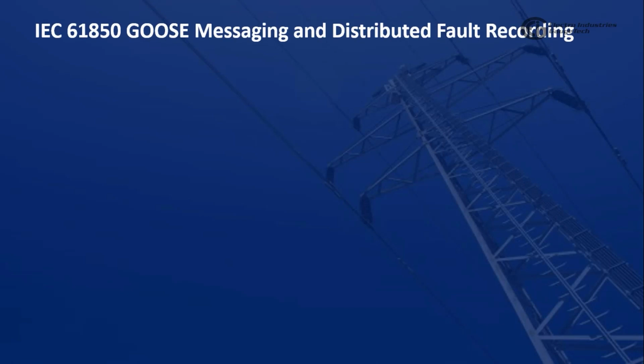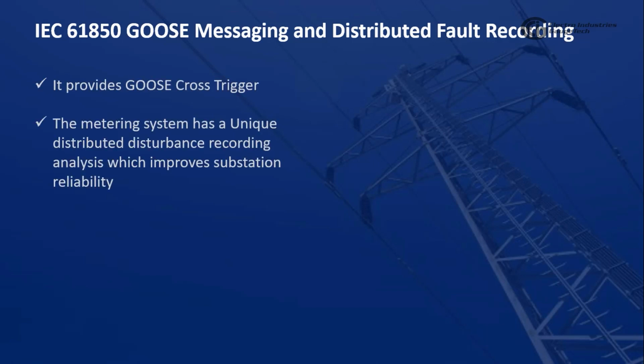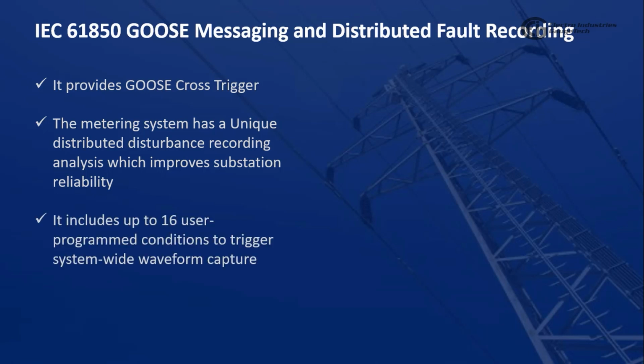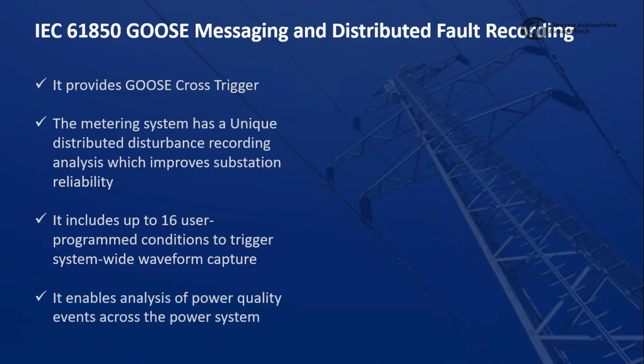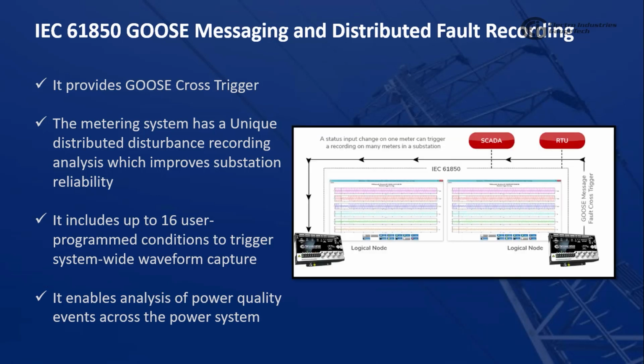Now, we move to another important feature of Nexus 1450 meter, which is IEC 61850 GOOSE messaging and distributed fault recording. It provides GOOSE cross trigger support. The metering system has a unique distributed disturbance recording analysis which improves substation reliability. It includes up to 16 user-programmed conditions to trigger system-wide waveform capture. It enables analysis of power quality events across the power system. The diagram here shows how EIG's distributed fault recording works.